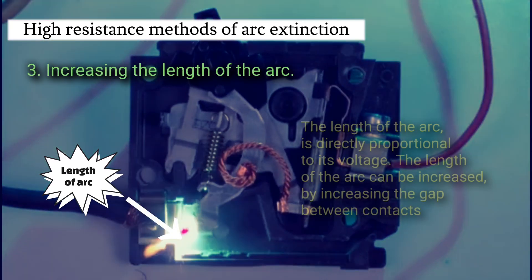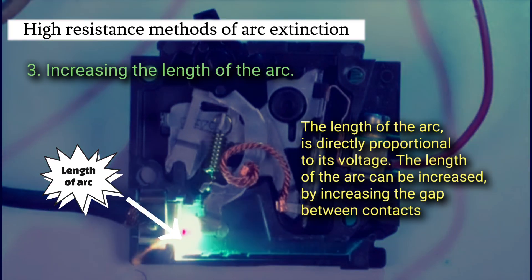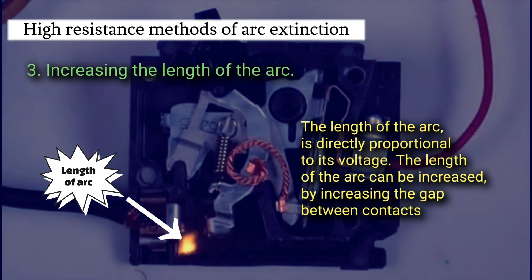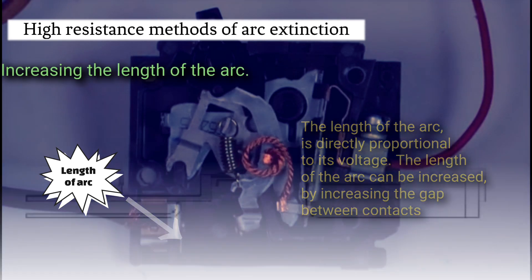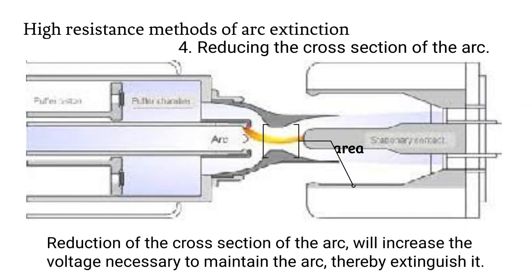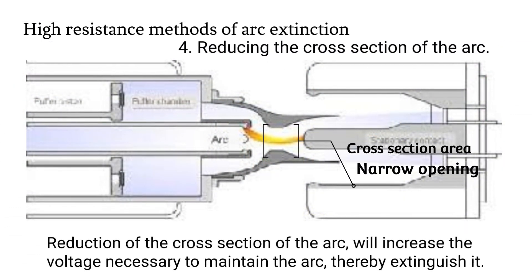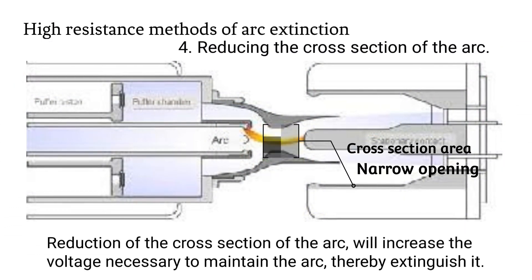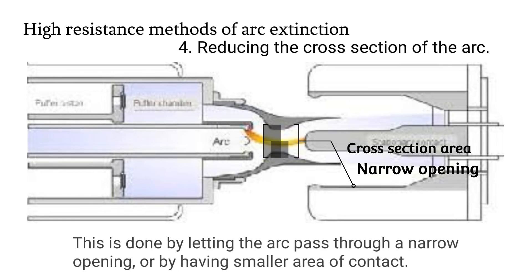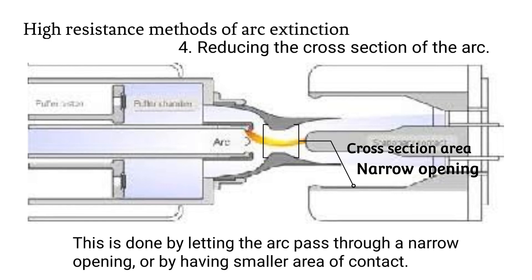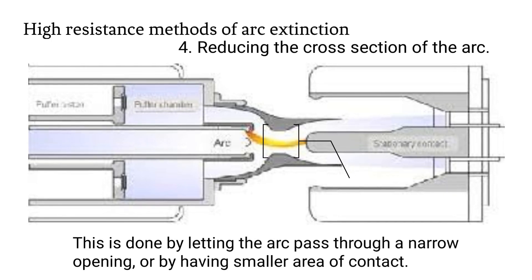Increasing the length of the arc. The length of the arc is directly proportional to its voltage. The length of the arc can be increased by increasing the gap between the contacts. Reducing cross section of the arc. Reduction of the cross section of the arc will increase the voltage necessary to maintain the arc, thereby extinguishing it. This is done by letting the arc pass through a narrow opening or by having a smaller area of contact.